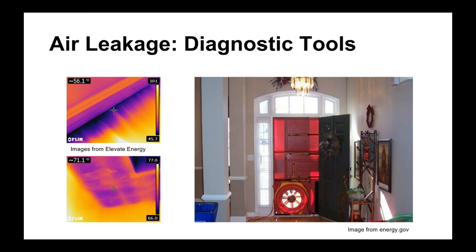You can also see fingers of cold air, which is useful when looking at windows. Windows will always have a pretty big temperature difference, so you're looking around them to see if air is flowing into the building. The top image shows a baseboard at the bottom of a room that hasn't been sealed at all — you can see the fingers of cold air coming in. The other shows a ceiling on the top floor of a building with an uninsulated roof, where you can see the hot air rising up to the cold blue area.